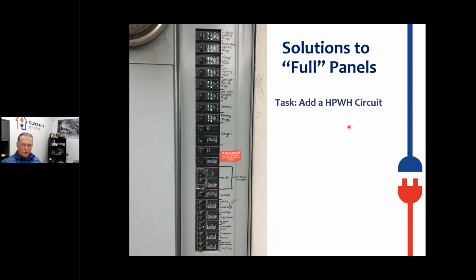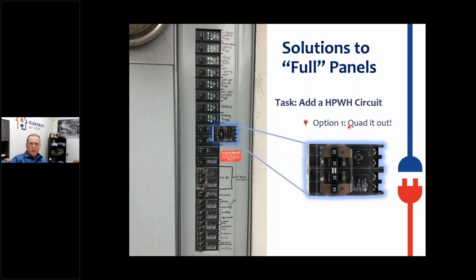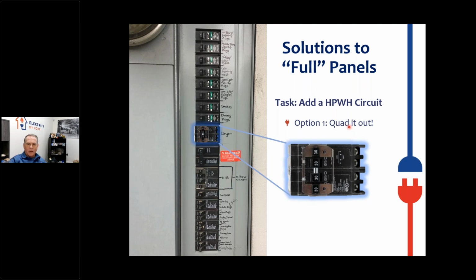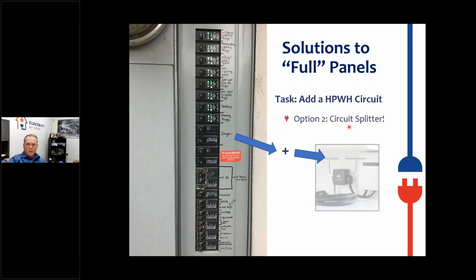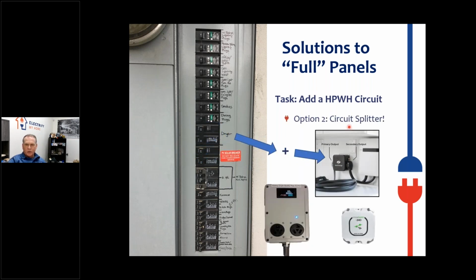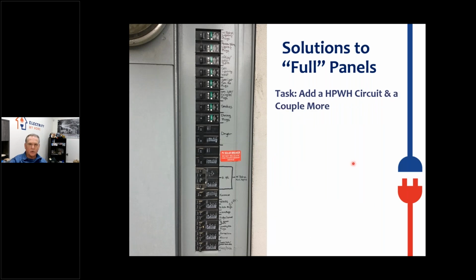Electric panels - solutions to full panels. We run into full panel problems all the time. Some of the solutions are put a quad breaker in, or a great circuit splitter. These devices allow us to use a single circuit for multiple units. This particular one is dryer on one side, heat pump water heater on the other, or split a car charger into 2 car chargers. Pretty cool thing.